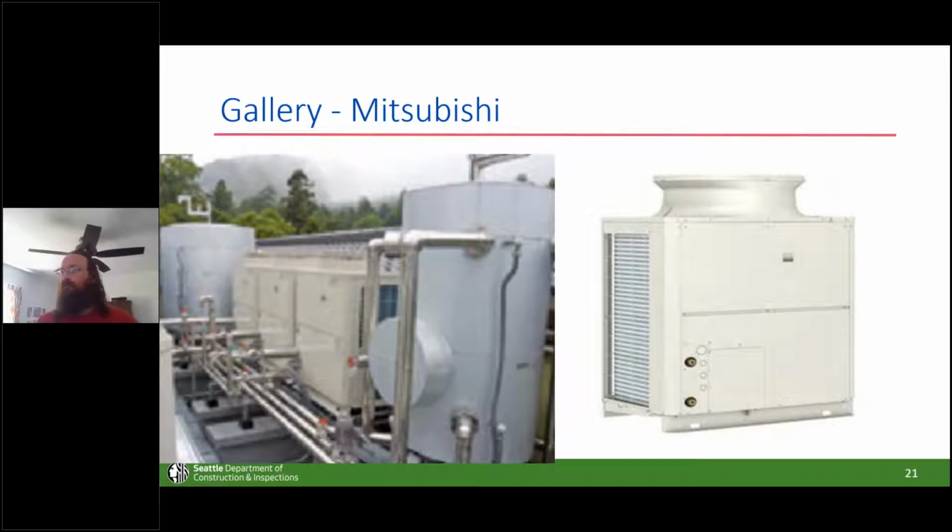temps. One thing to mention is that they only offer one unit, one model number for the QAHV, but it has 3 different modes of operation: a 40 kW, 50 kW, and 60 kW. What the 40 kW setting does is it limits the capacity, flatlines the capacity with still the same infrastructure in the unit. And that prioritizes the COP. But you have that 60 kW input that you could switch to, say it was a colder time of year or something where you really need to push the envelope and get more heat into your water. That's an option as well. It's just going to dip your COP down.